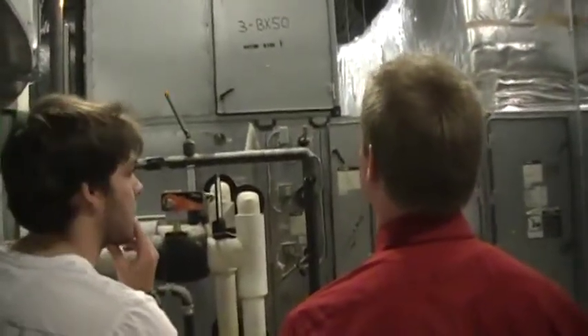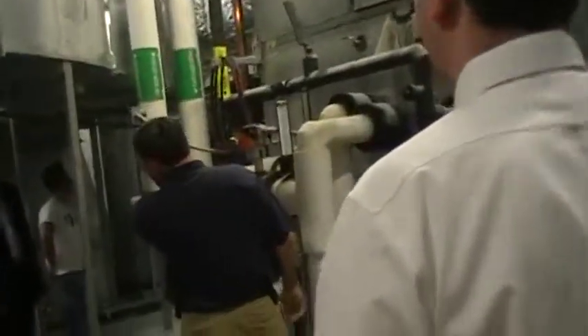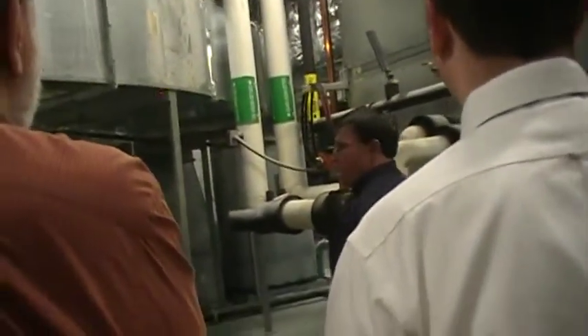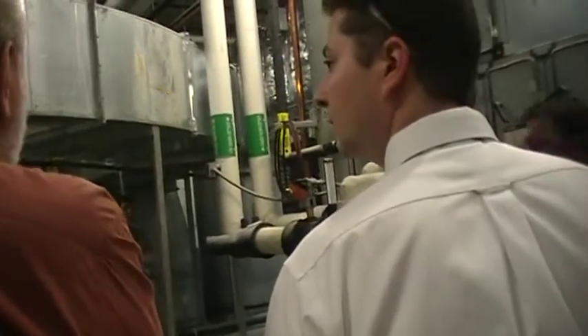On this system, you've got a supply fan that is blowing air into the space. And then when we were looking at that duct at the back of the room, you've also got a return fan that's pulling the air back out of the room. Comes around, comes through, goes across, this is where we're getting the chill water from the central energy plant, which is coming out of that, where he's talking about the shaft. That chill water goes down to the main mechanical room. When it comes up here, goes through here, and we're modulating this control valve for this air handler to put out 55-degree air. And this is really chilled water.